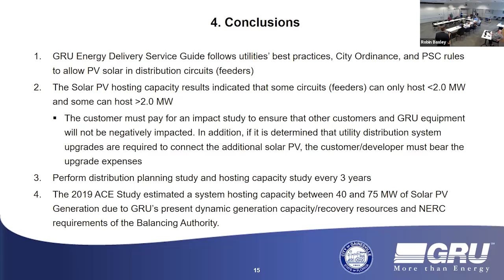This is real, it's not make believe, but it does kind of turn old distribution engineering on its ear. Because you used to worry about low voltage, well out on the feeder. Now we're talking about high voltage along the way, because it must be injected somewhere along the way with the inverters.